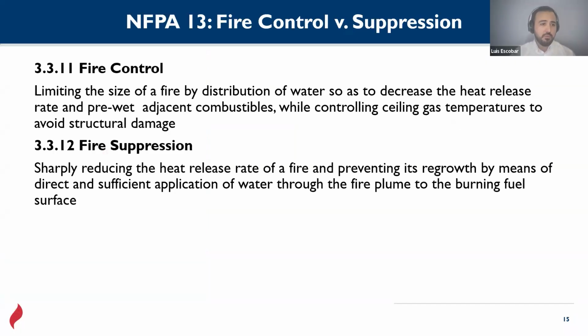All right. Fire control: limiting the size of a fire by distribution of water so as to decrease the heat release rate in pre-wet adjacent combustibles while controlling ceiling gas temperatures to avoid structural damage. What we do with fire sprinklers is to release water from those sprinklers, obviously. And besides extinguishing the fire by itself, the one that is already happening, we spread water throughout that area so the rest of the material can be wet and the fire doesn't spread too quickly. It's one of the purposes.